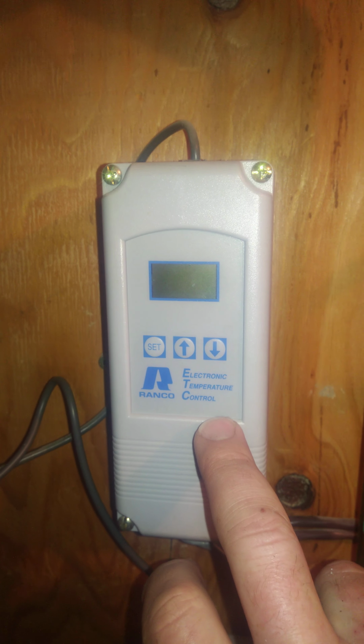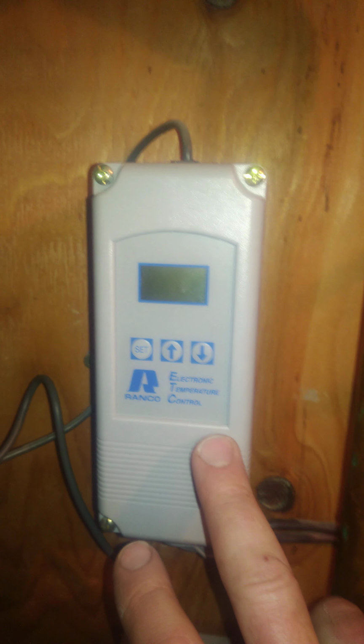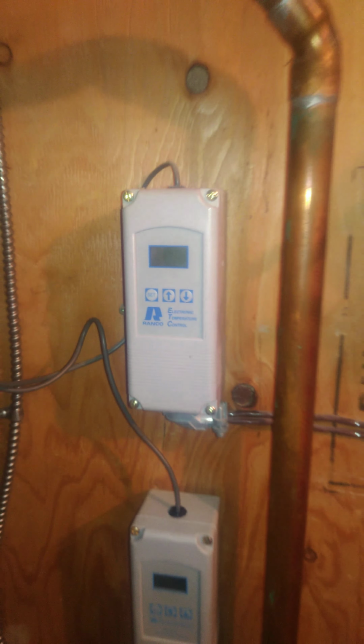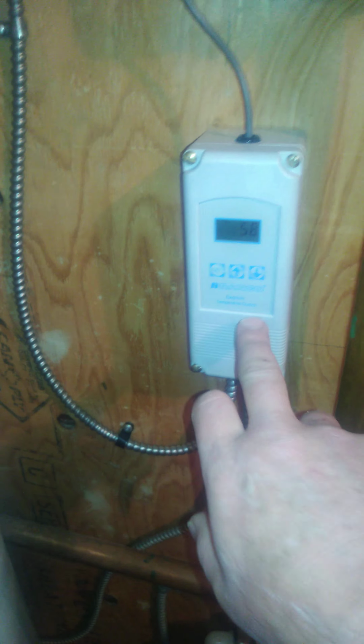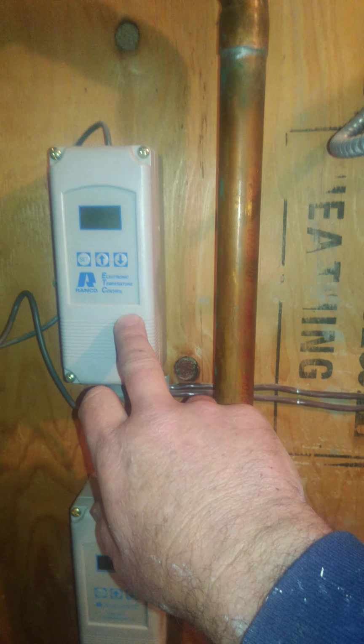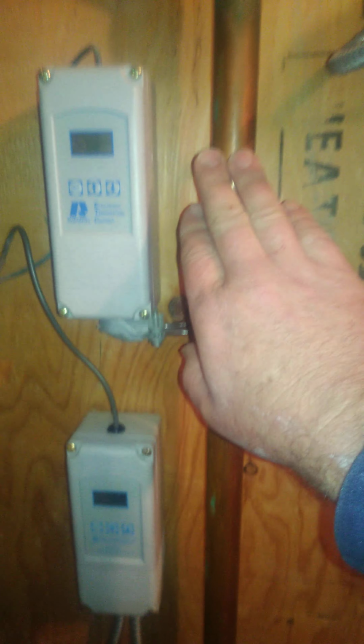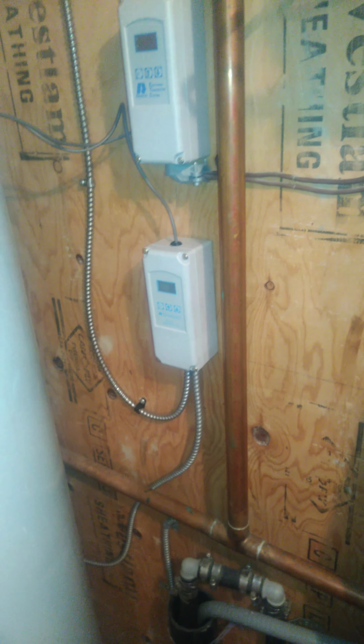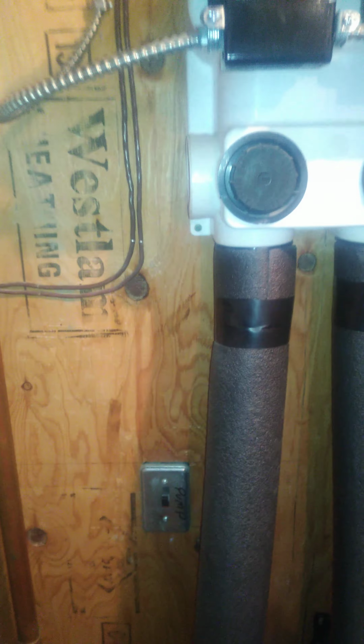The differential was down to 92, if I recall, so at 92 degrees it would come back on again. Now that I've added this system, this unit basically cycles on and off before that temperature is reached. So if things work out, my Geo should never really come on in the wintertime. In the summer, we'll definitely use it for cooling, and it does an excellent job in that mode, because you're bringing water in at around 55 degrees, so it doesn't have to work near as hard to give you 70 degree air through the ductwork.